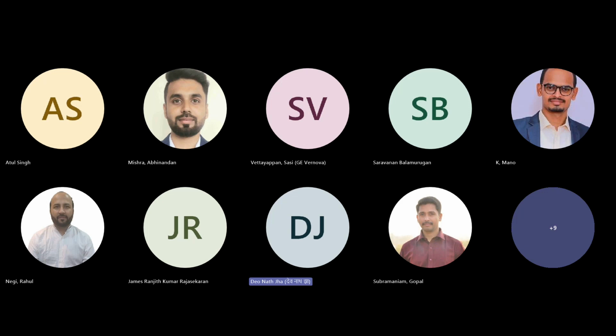Multiple ML programs are being used there, starting from XML parsing to extract the relevant features from an FRA signature. Then we have used random forest for model building along with hyperparameter tuning. And then we are integrating COMSOL libraries with that model to develop a mechanical model visualization.